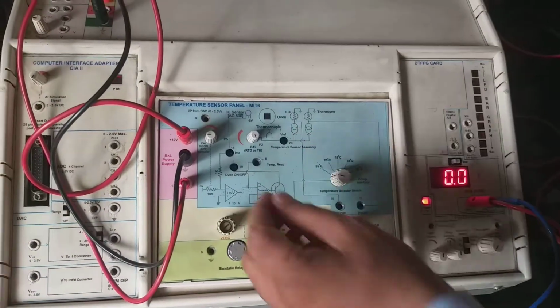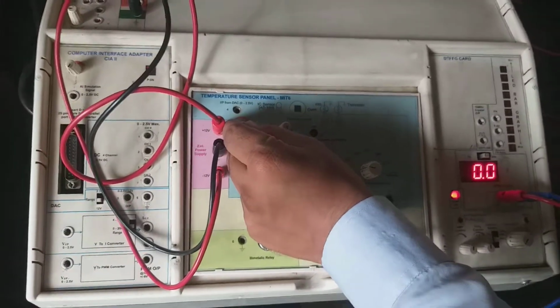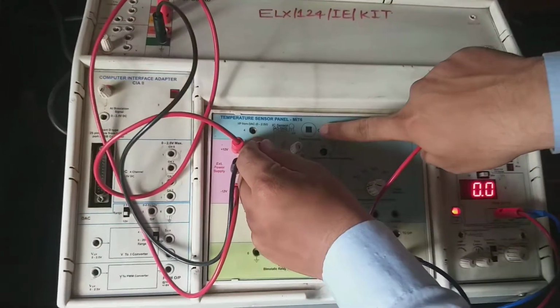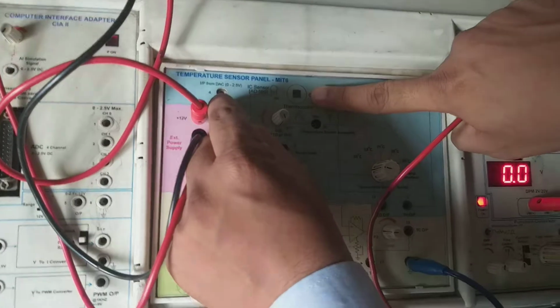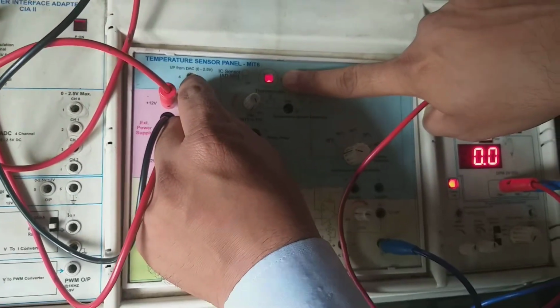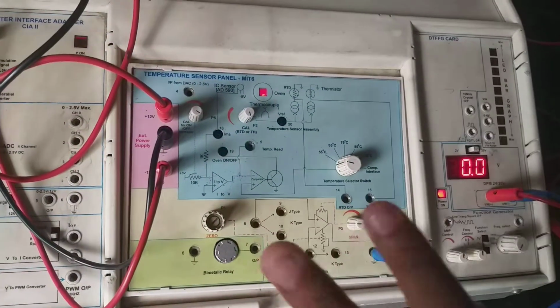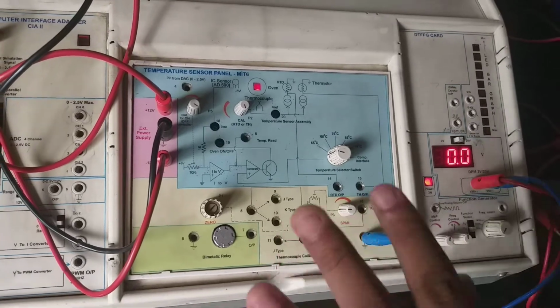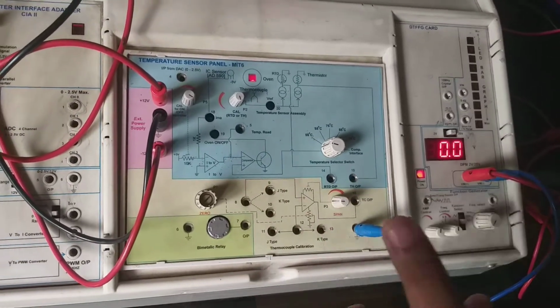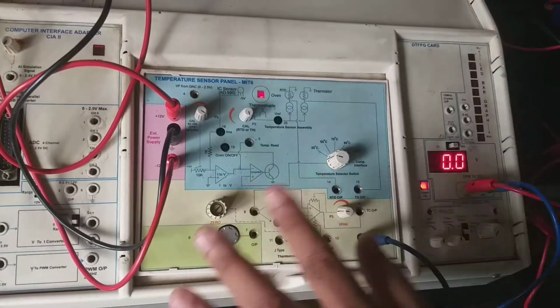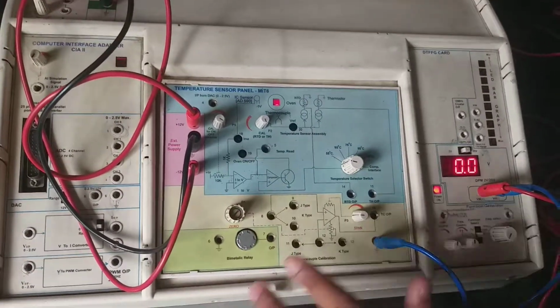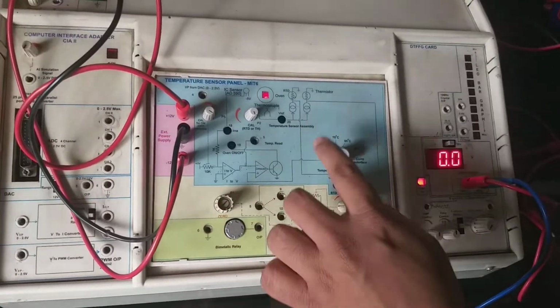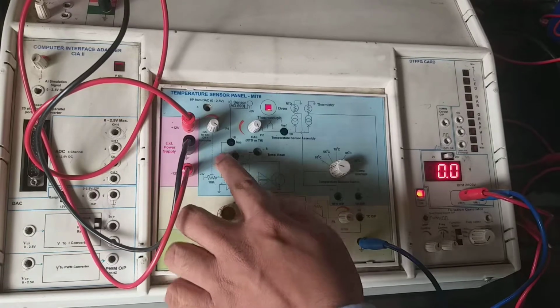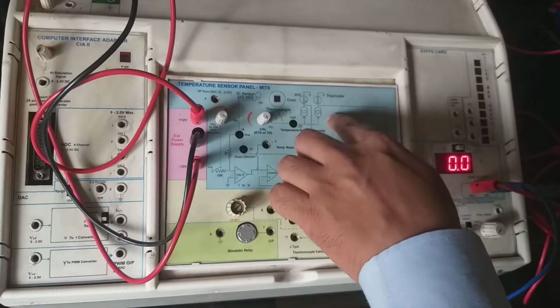If the oven is not started, then move this calibration pot in such a way that this LED indicator turns on. When this LED indicator turns on, it means the oven starts heating. At that point the oven has started heating, and the LED is glowing, indicating that the oven is heating. This above setting is required to calibrate the AD590 as well, and the thermistor or RTD.